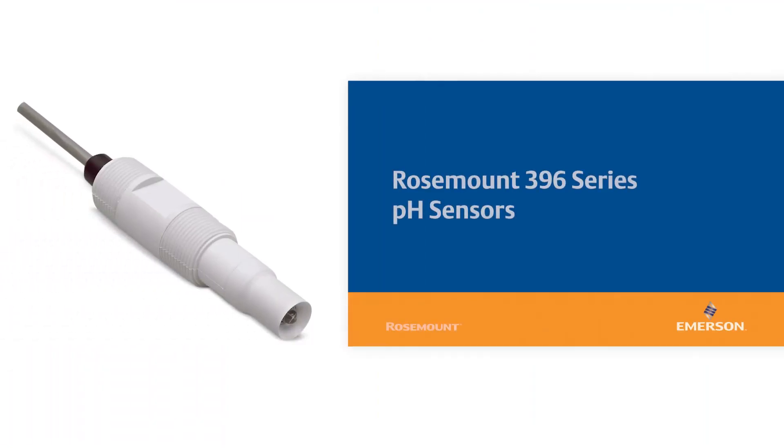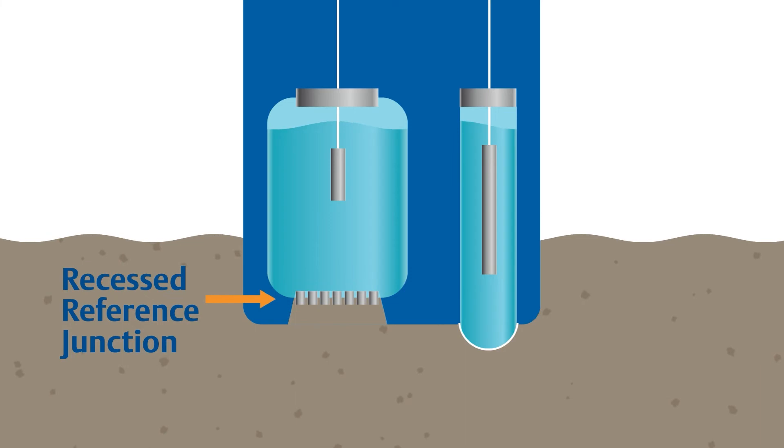Rosemount 396 series pH sensors are designed to overcome these challenges. These sensors feature a recessed reference junction with larger surface area to minimize the effects of coating and ensure uninterrupted ion flow even in dirty water applications.